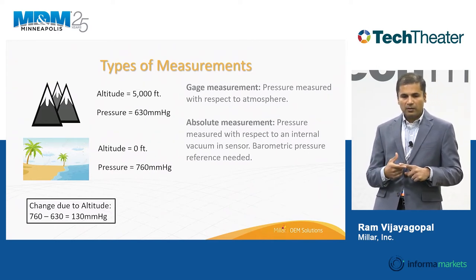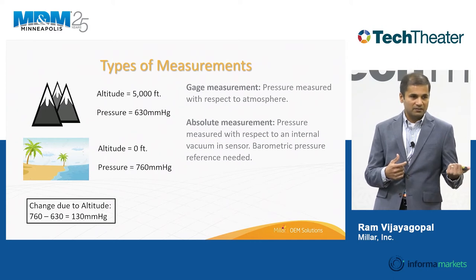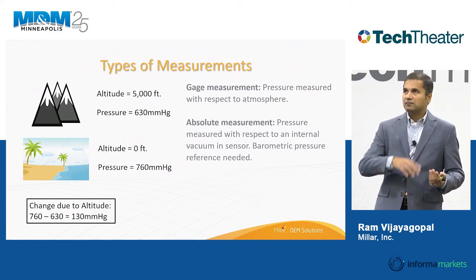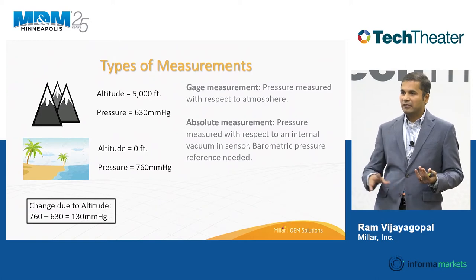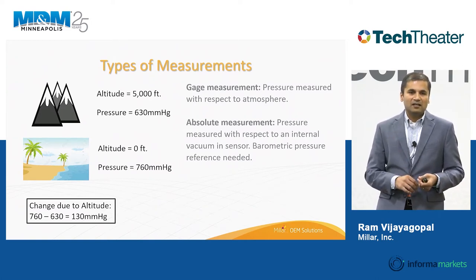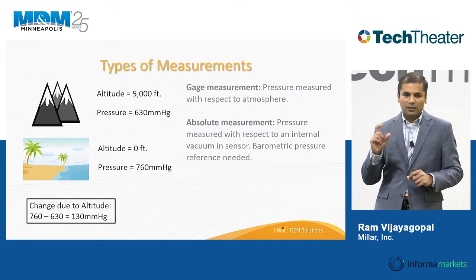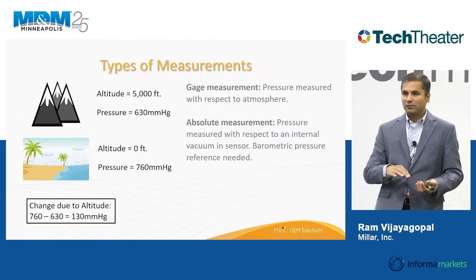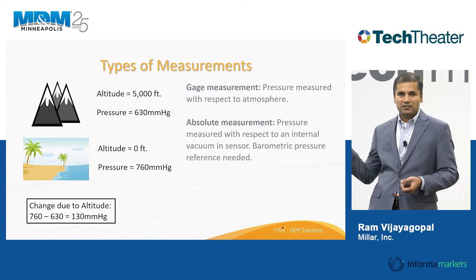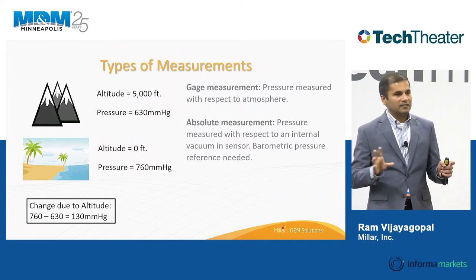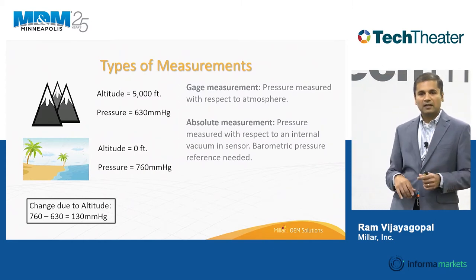Many applications cannot afford a wider lumen catheter, so if you're talking about implantable devices or pressure sensing in tortuous vasculature, you're pushed to an absolute measurement. Absolute measurement measures pressure with respect to an internal vacuum, and the system requires a barometric pressure reference. On any given day, barometric pressure changes by five to six millimeters of mercury, and that kind of change can completely derail the clinical signal physicians are expecting to see.